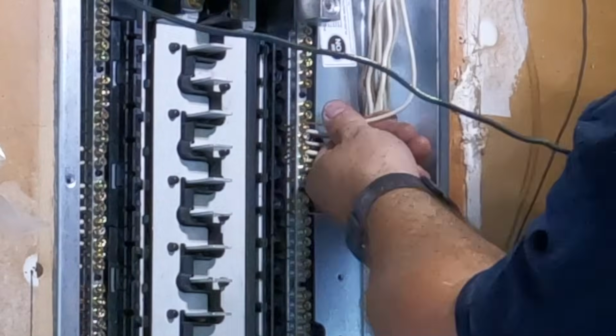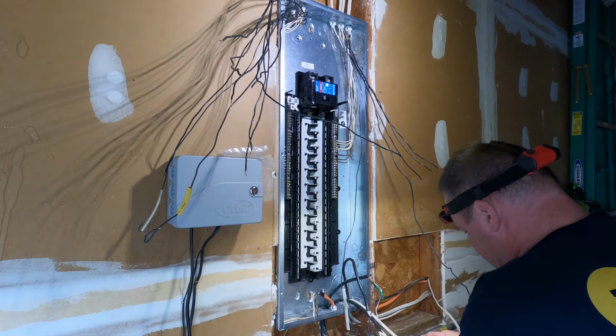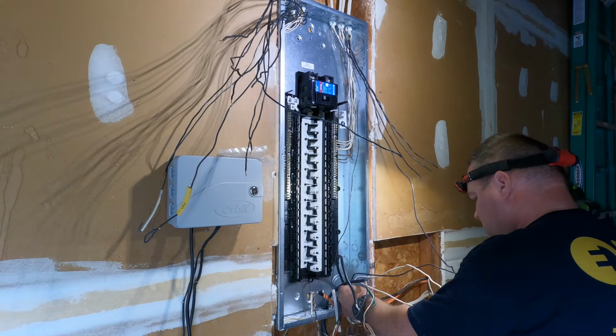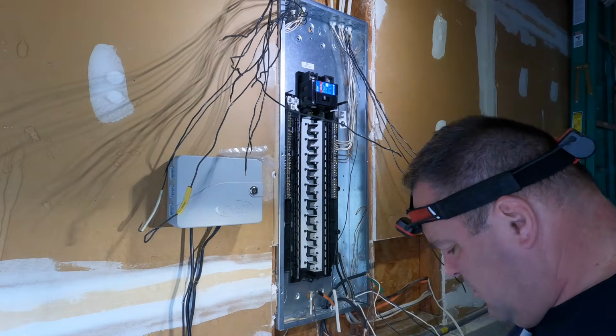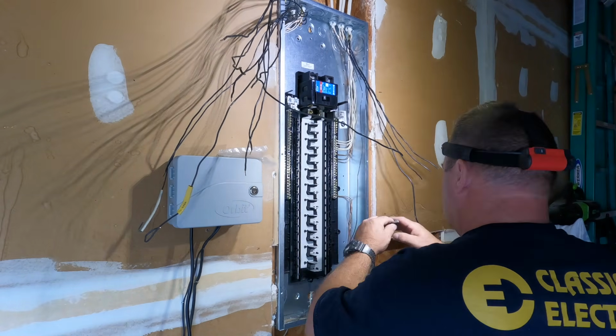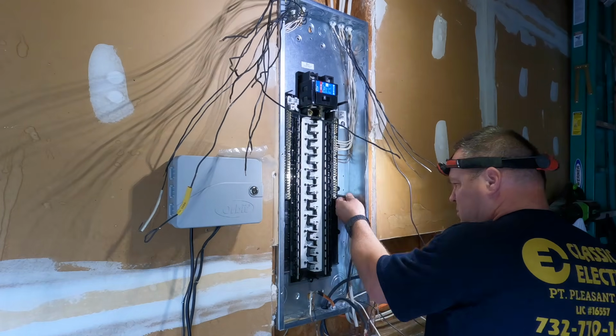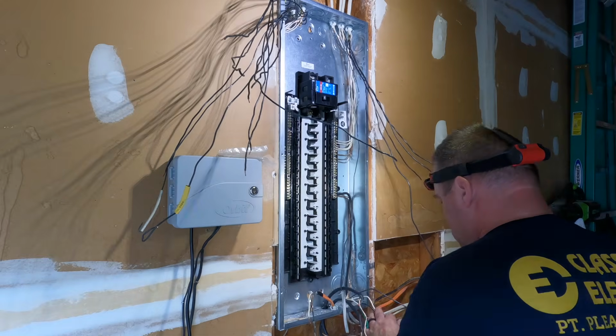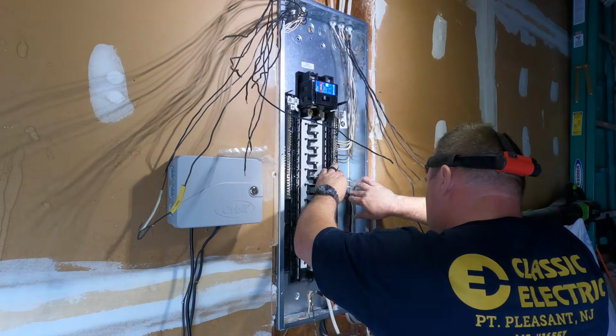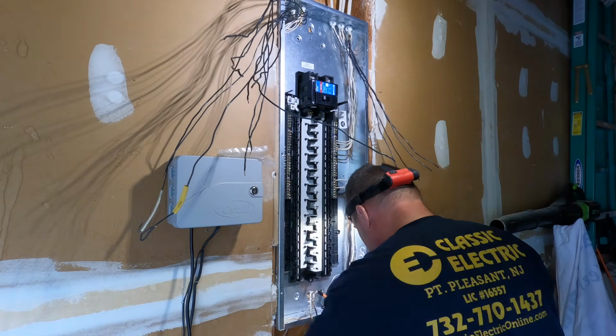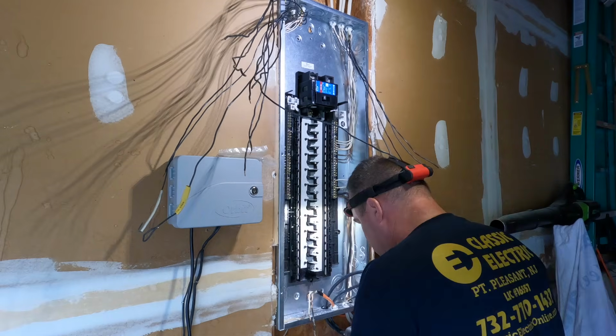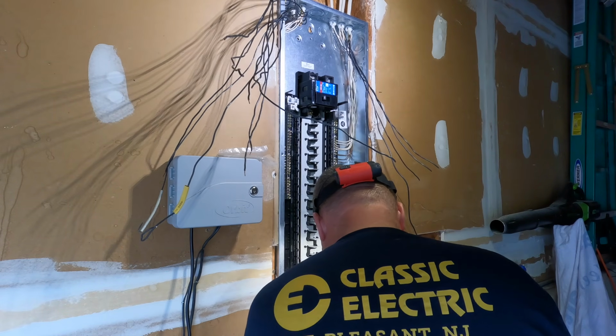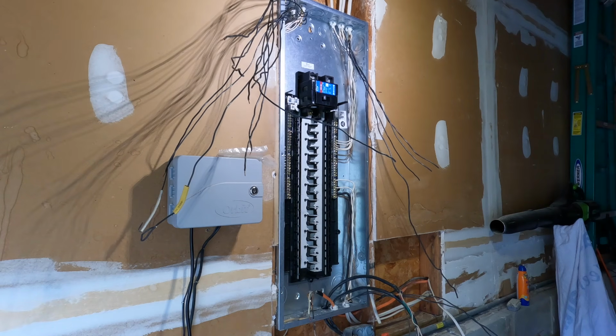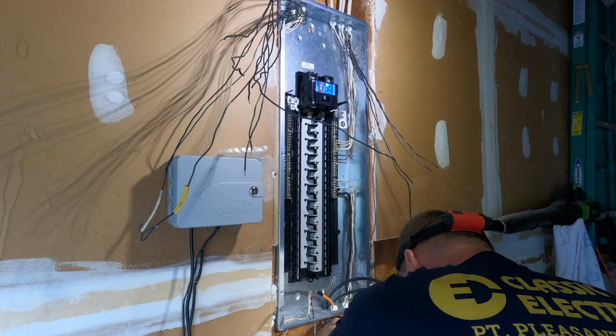For the equipment grounding conductors, you can put two of them under one terminal as long as they're the same size, but you cannot do that with a neutral conductor. The reason you can't do that with a neutral conductor is that most neutral conductors are current carrying conductors. And if you don't have a nice secure termination on that terminal, arcing could occur. And if you have arcing, not good.